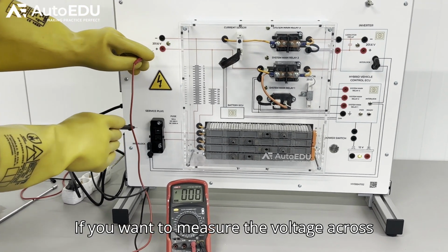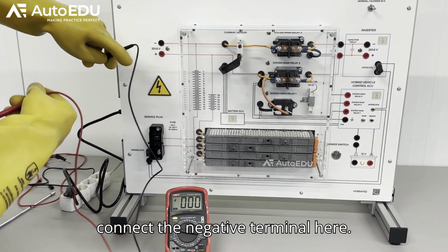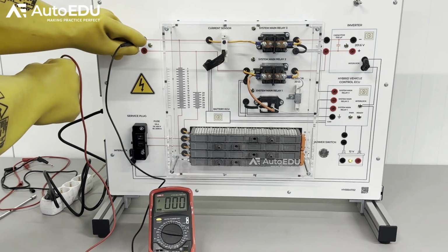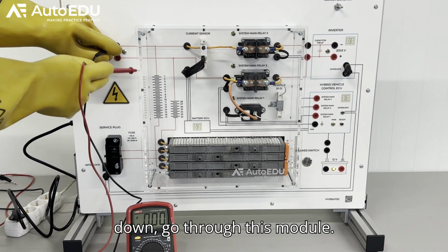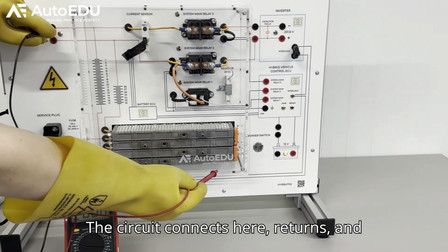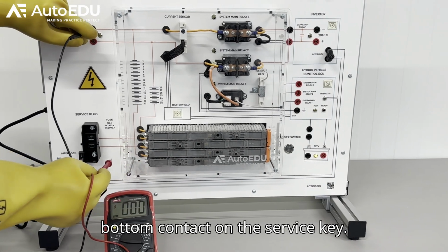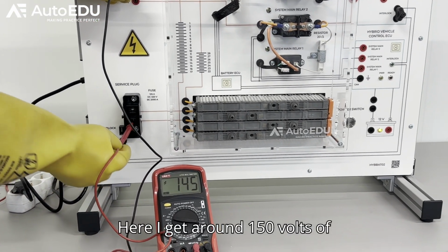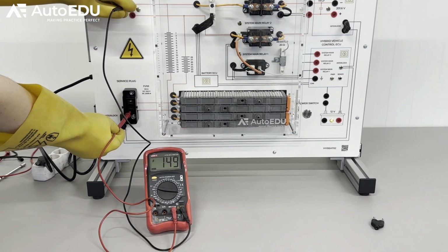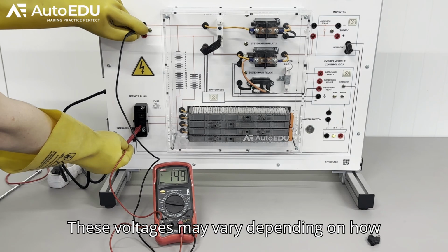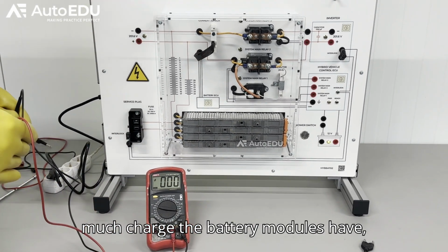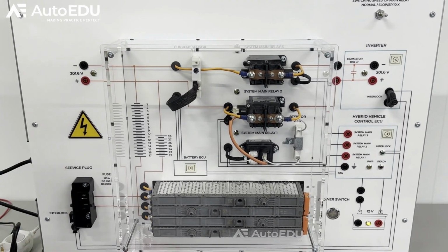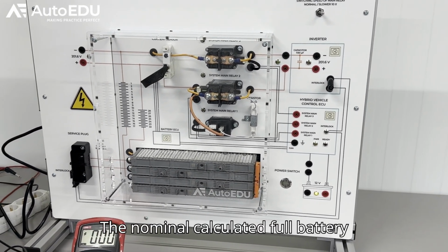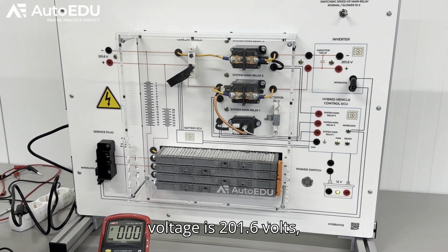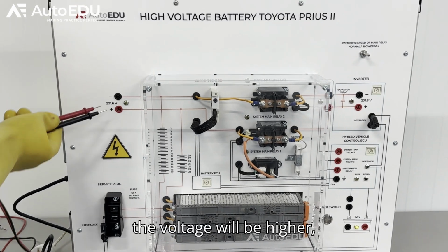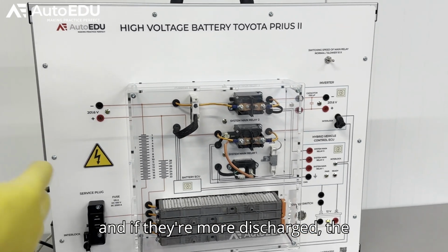If you want to measure the voltage across a larger part of the battery, I choose to connect the negative terminal here. I follow the wires. They go through a larger section, drop down, go through this module. The circuit connects here, returns, and that means I need to connect to the bottom contact on the service key. Here, I get around 150 volts of direct current. These voltages may vary depending on how much charge the battery modules have, how charged they are. So the voltage may vary. The nominal calculated full battery voltage is 201.6 volts. But if the batteries are more charged, the voltage will be higher, and if they're more discharged, the voltage will be lower.